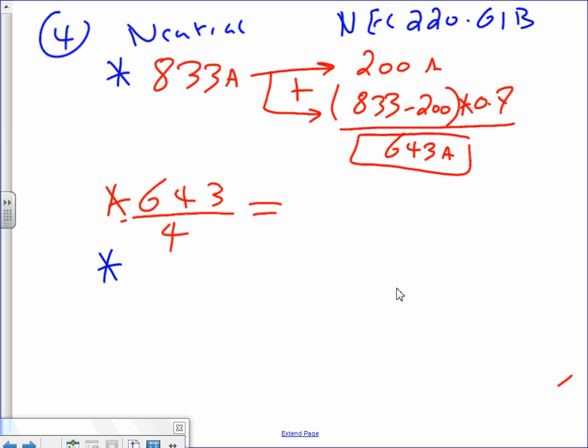So Gary, if you parallel the phases 4 sets, the neutral must be what? 4 sets. Can you parallel the phases 4 sets and the neutral 2 sets? No, they have to match. Because you're putting them in the same conduits, guys. Remember, here's a 3, here's 1 set. Can you guys see that? If there's another set, they must have a neutral in it.